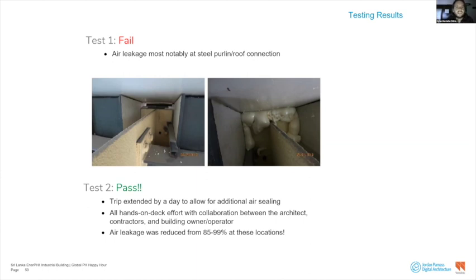You can sort of see it in the photo on the left - there's some daylight coming through, and that was a condition that happened like 30 times in the building. It was a huge chunk of leakage. When we had the fans running, we got up on a 15-foot ladder and stuck our hands up there, and you could feel the air blowing out.